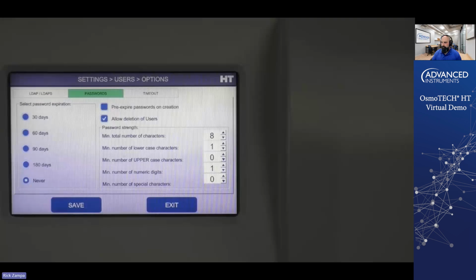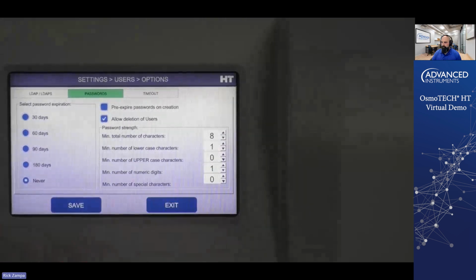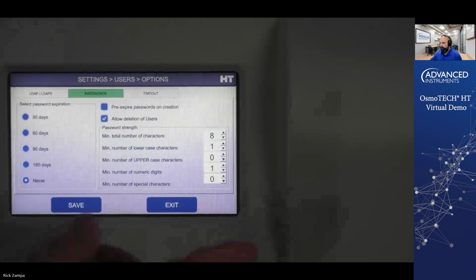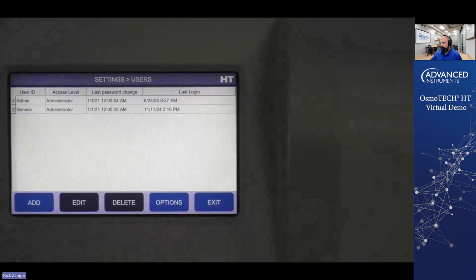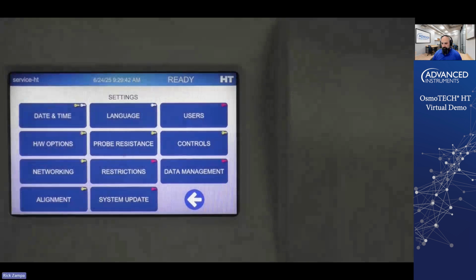Another thing you see on this menu is passwords. This is where you would set up your password strength if you were manually entering the users on the instrument through the touchscreen display. This allows you to choose just how many characters, what type of characters, and to set up when passwords expire. If you're using LDAP, all of that is still managed by your IT department under their rules and regulations for your Windows or your daily user logins. Exit out of this menu. So that's how you add users and how you would set up your user functionality for the instrument.